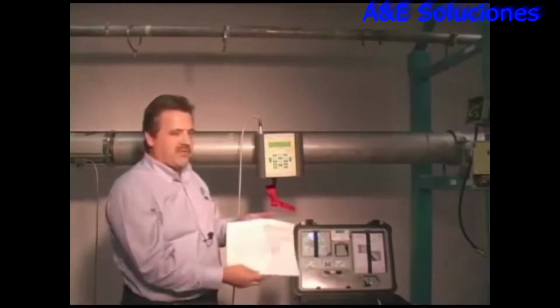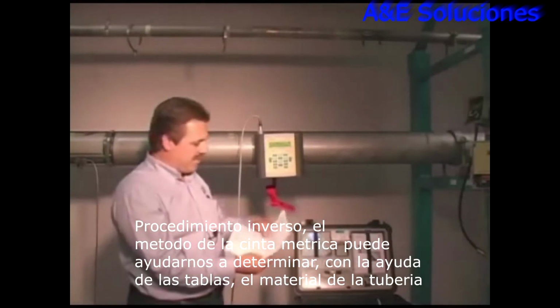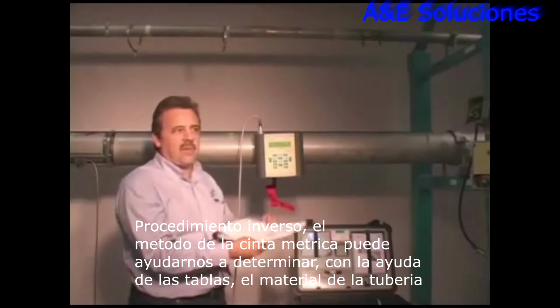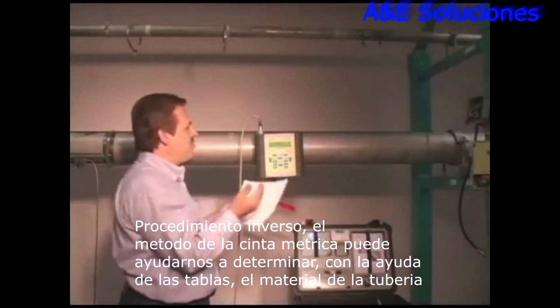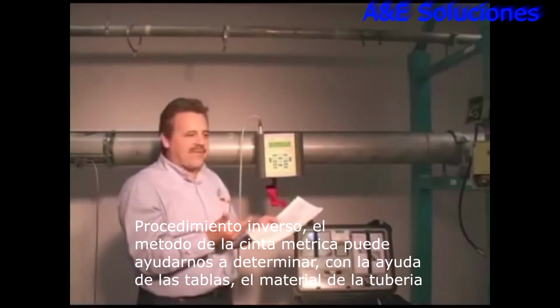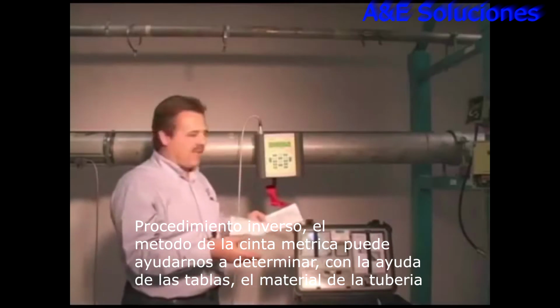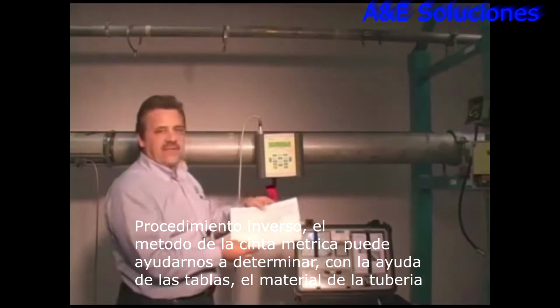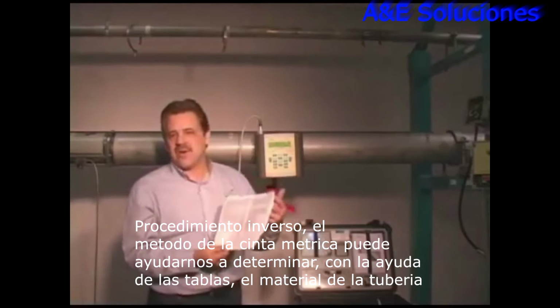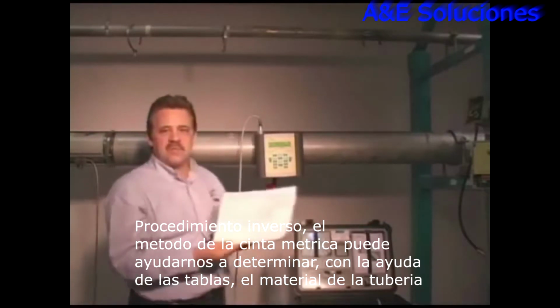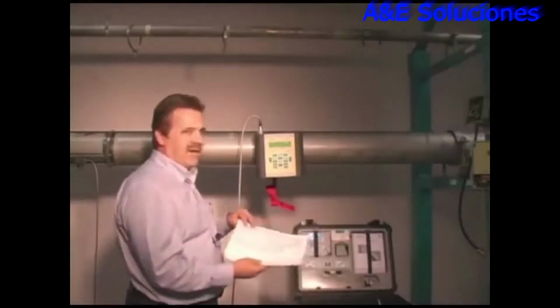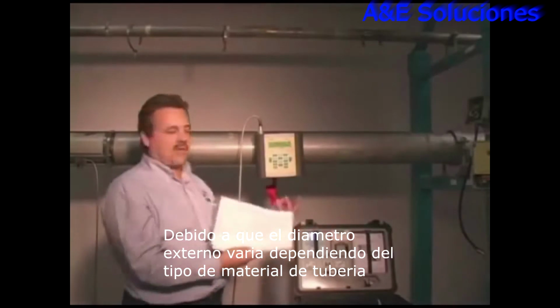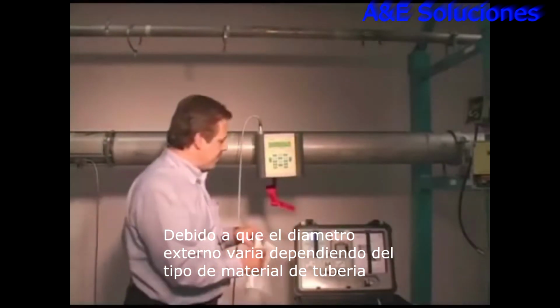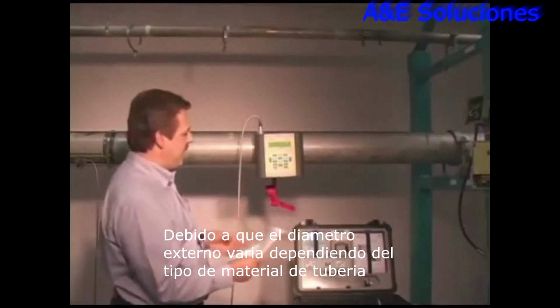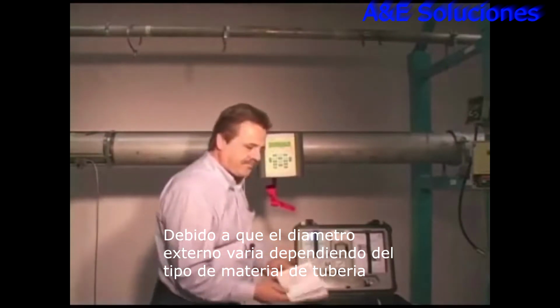There's also pipe charts in here for copper pipe. You'll sometimes come across a ductile iron pipe or cast pipe, and you're not sure if it's a carbon steel or cast. By measuring the outside diameter and finding out where it fits on the pipe chart, that'll help you determine, do I have a carbon steel pipe or do I have a cast iron pipe? Because cast iron has different nominal dimensions than carbon steel. Stainless happens to be the same nominal dimensions as carbon steel.